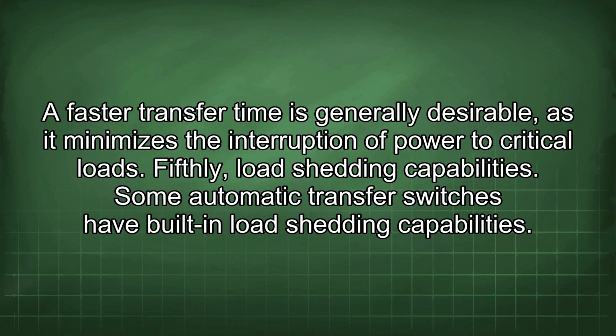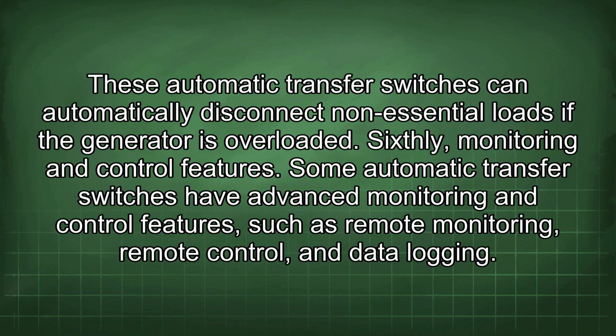A faster transfer time is generally desirable, as it minimizes the interruption of power to critical loads. Fifthly, load shedding capabilities. Some automatic transfer switches have built-in load shedding capabilities. These automatic transfer switches can automatically disconnect non-essential loads if the generator is overloaded.